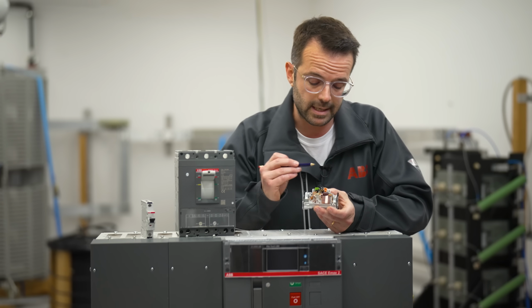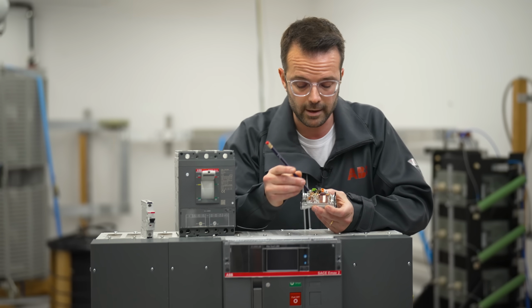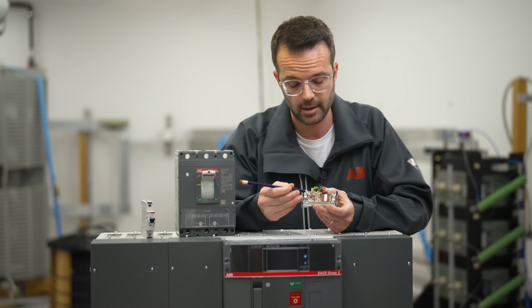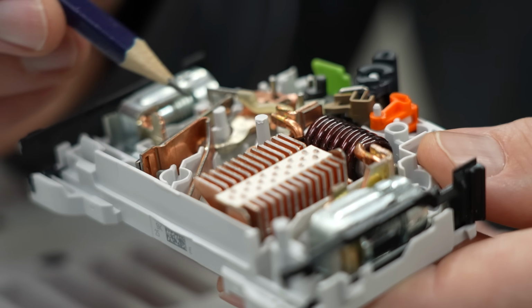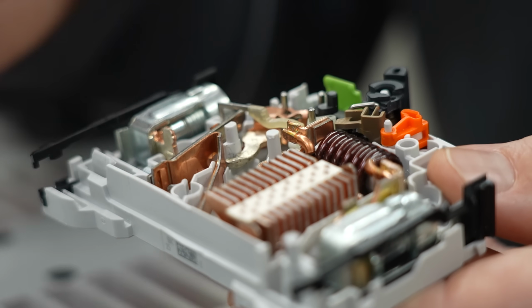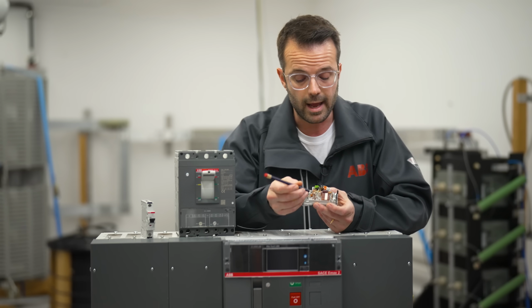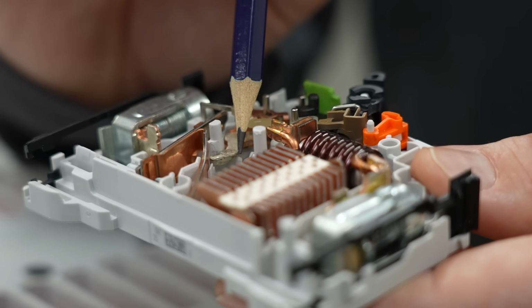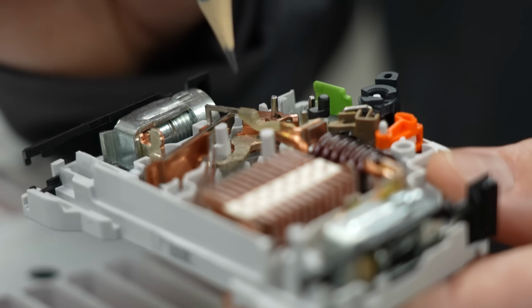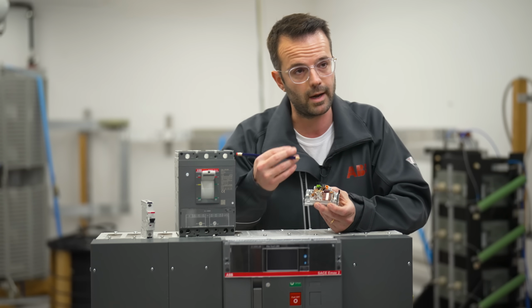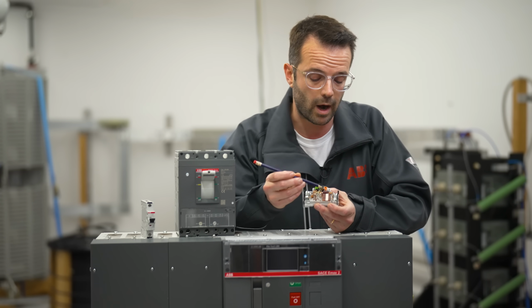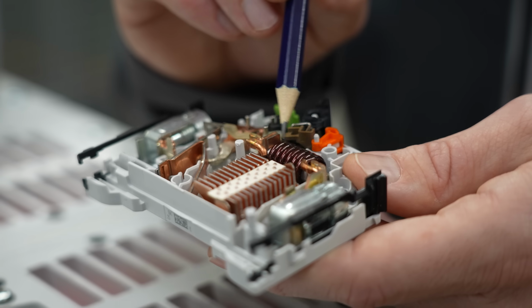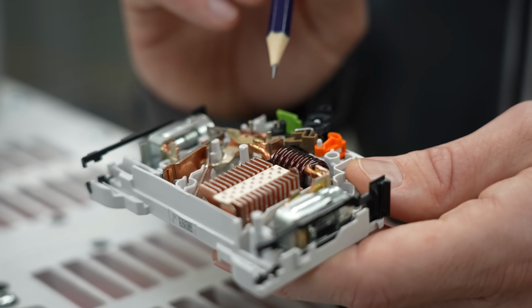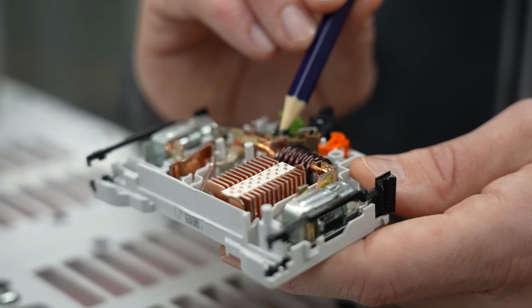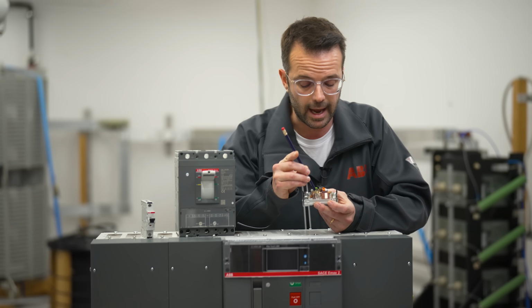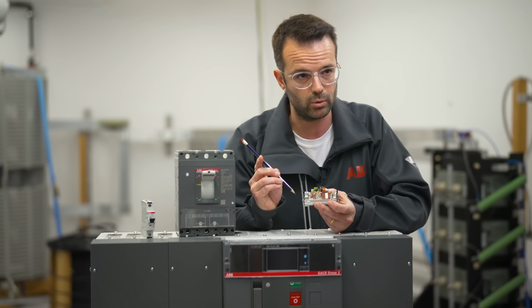The idea is that as soon as one of these two devices, a thermal device, feels a small surge in current from overload and overcurrent, it's going to snap the mechanism so that the two contacts you can see here open and try to interrupt the current. For larger currents, we have a magnetic strip here, which also kicks the contact above and again opens the two contacts.